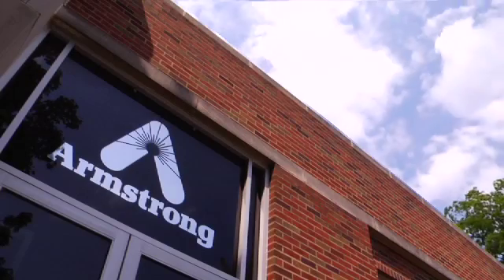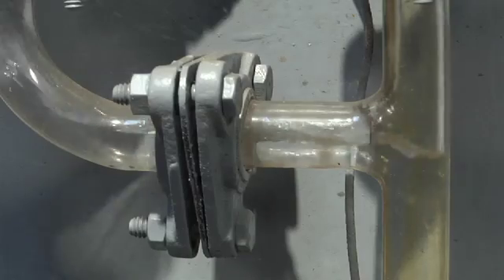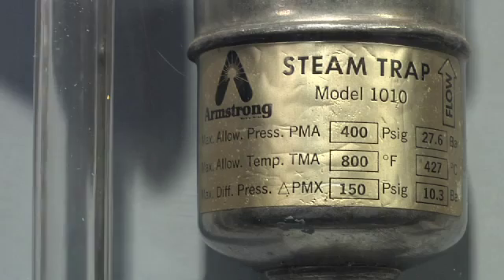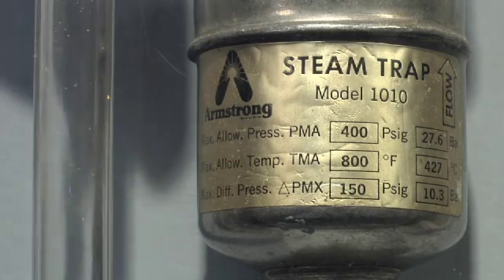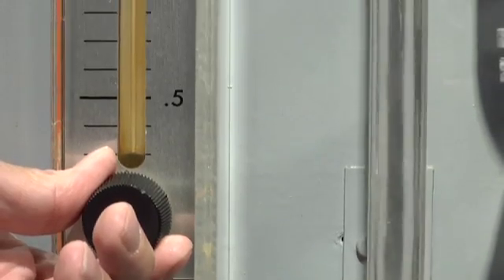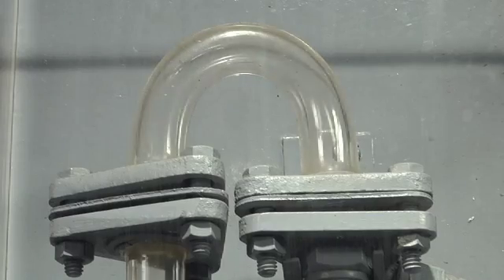Today's demonstration is intended to show the difference in operation between two types of steam traps, specifically the thermostatic bimetal trap and the inverted bucket trap. We will be focusing on each trap type's ability to drain condensate from the equipment as it forms.